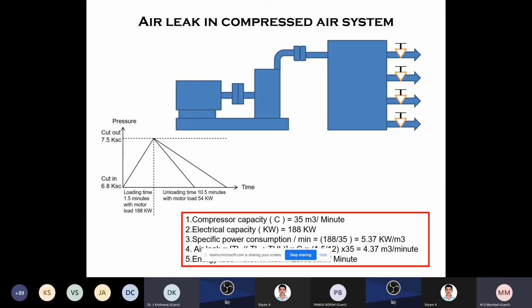Now stray losses. Basically, compressor. The efficiency of the compressor is very less. So compressor leak can be calculated with a very easy formula. You have to start the compressor and see how much loading time it takes. You can see the current and use a stopwatch. So loading time you will get it. And the loading and unloading time is also measured. So loading time divided by total time, into percent, is called the leakage as a percent of capacity. If the leakage is more, you give the recommendation accordingly. That is called the leak test. So the compressor system, very easily you can find it out.